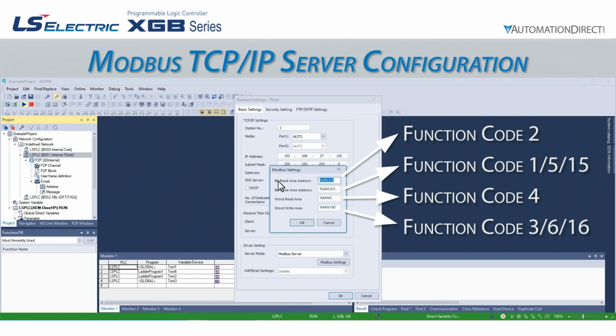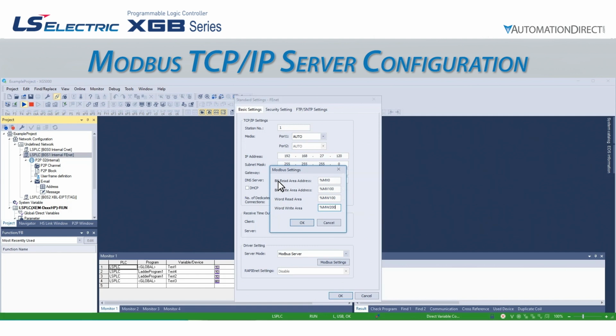Let's set our bit read area address to %MX0 and our bit write area address to %MX100. We will then set our word read area to %MW100 and our word write area to %MW200. The direct variables listed here will be accessible at the first Modbus offset address and will increment with each offset. For example, if we wanted to read %MX2 or %MW102, they would both be available to the Modbus client at the third offset address using the corresponding function code.